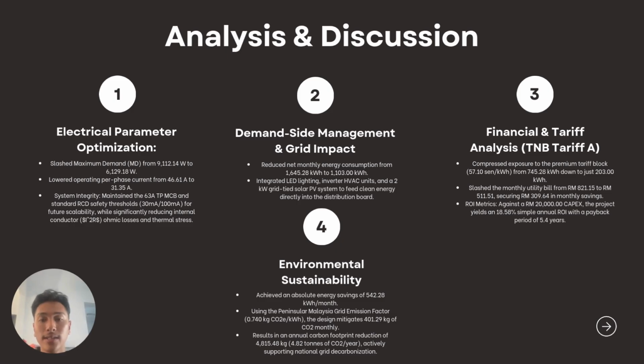Thank you. For the analysis and discussion, the first is electrical parameter optimization, where we slash maximum demand from 9,112.14 watt to 6,129.18 watt. We lowered the operating per phase current from 46 to 31, and the system maintains the 63A TP MCB and standard RCD thresholds, which is 30 mA over 100 mA, for future serviceability, while significantly reducing internal conductor ohmic losses and thermal stress.